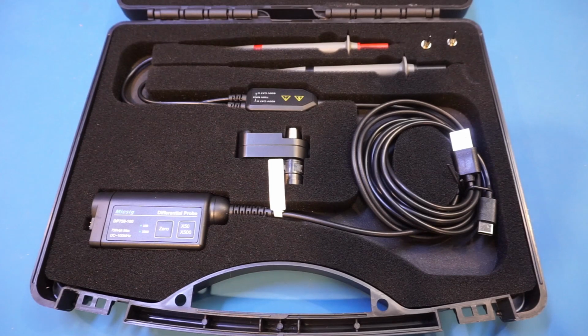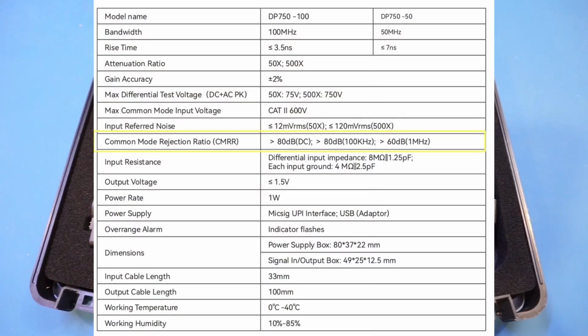For instance, the common mode rejection ratio, or the CMRR, is much improved for the DP750. Under low frequency, the CMRR is greater than 80 decibels, which is the same as the older DP1000 series. But as the frequency increases, there are some noticeable improvements. For instance, when the frequency is greater than 1 MHz, this new probe has a CMRR of greater than 60 decibels, whereas the 1000 series has a CMRR of just above 50 decibels.